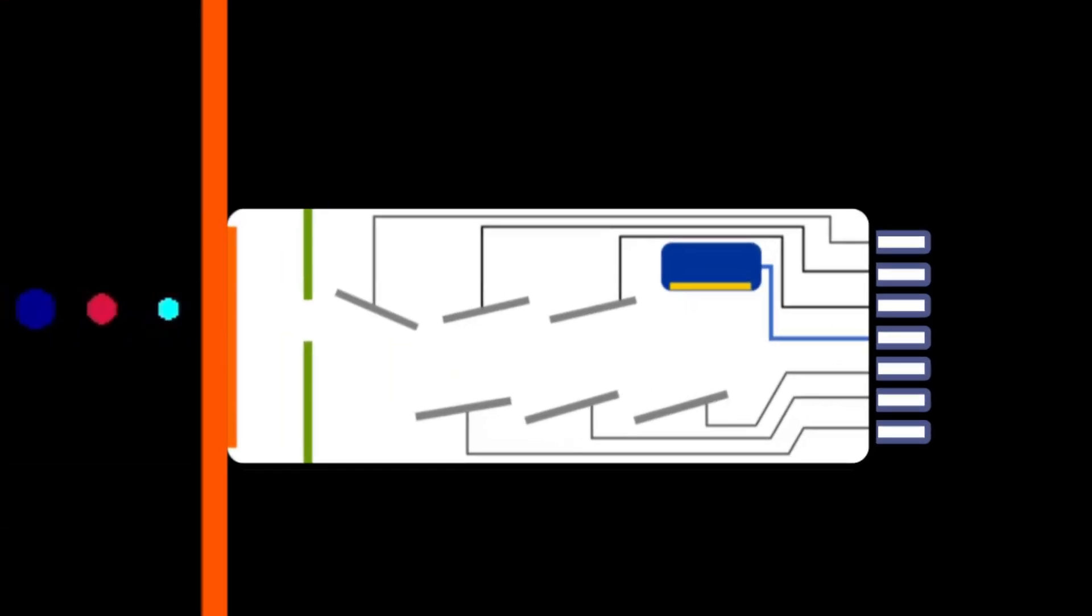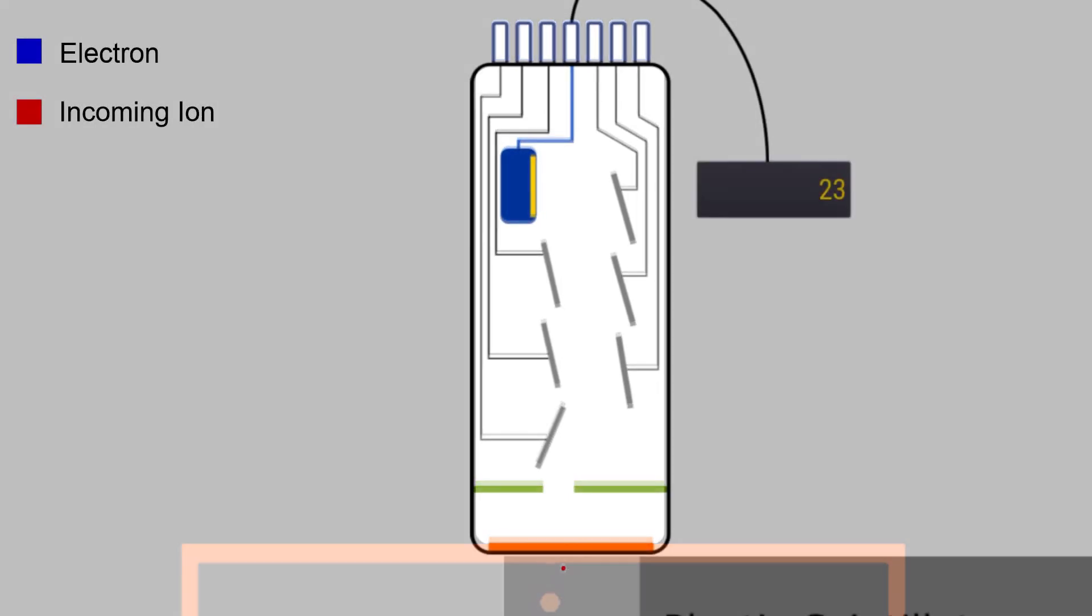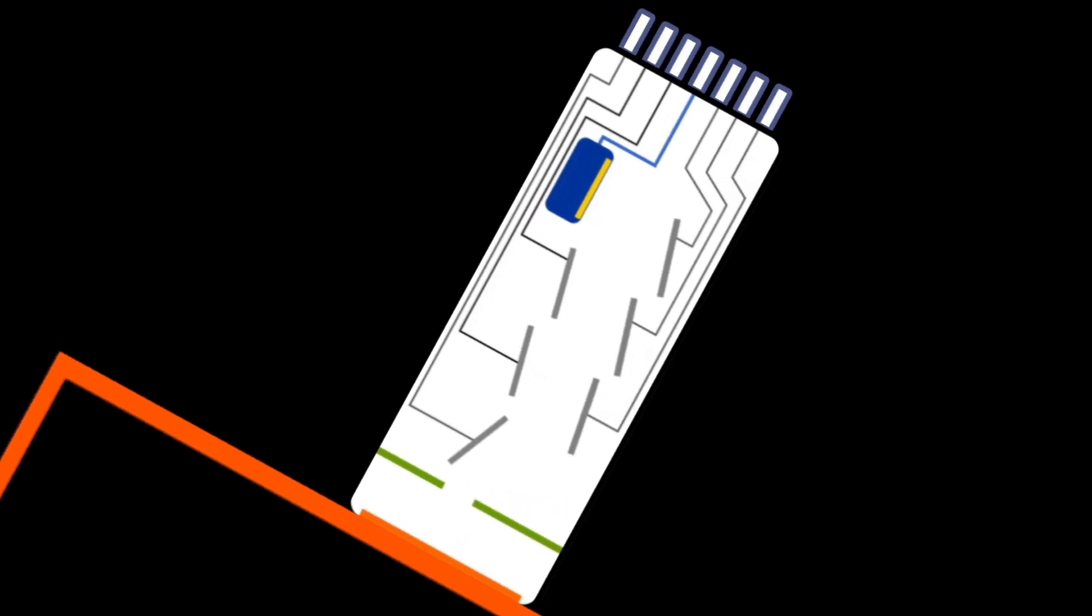Let's start with the stream of ionized particles and let's assume that they're all positively charged. They don't have to be. This stream will flow through a box that's currently empty and out the other side into an ion detector. A quick note on ion detectors. There are many kinds of ion detectors, but the one we are using in this example is an electron multiplier. This detector works in the following way. When an ion hits a sensor in the detector, it knocks off secondary electrons. These secondary electrons hit the next sensor in the chain, knocking off even more secondary electrons. The beam of secondary electrons becomes stronger and stronger after each interaction with the sensor. Eventually, this beam of electrons is sent to an electronic circuit that measures its intensity or current. So that's how an electron multiplier ion detector works.